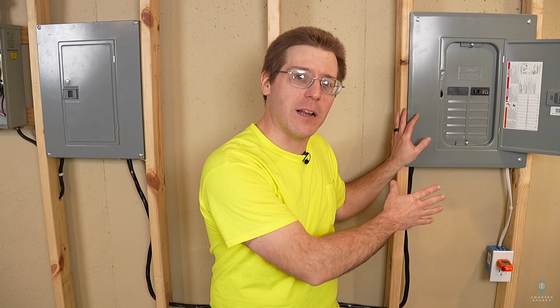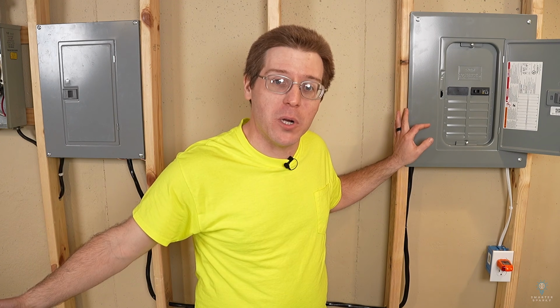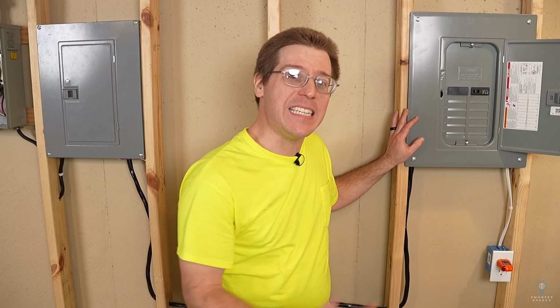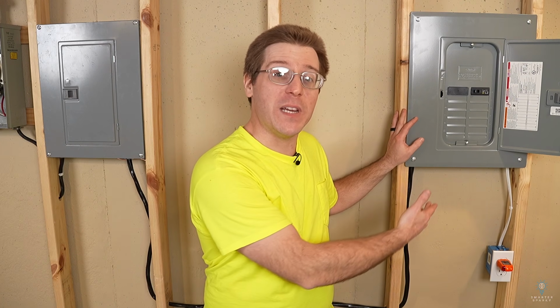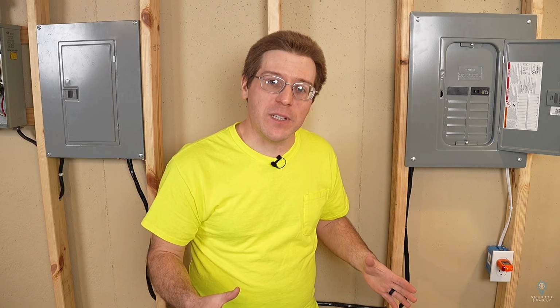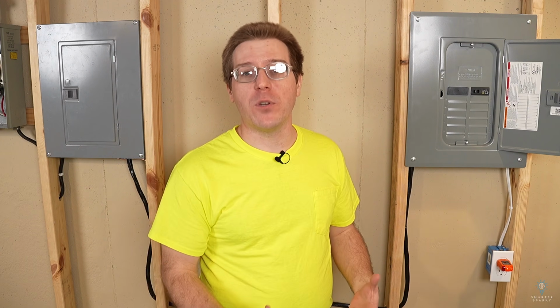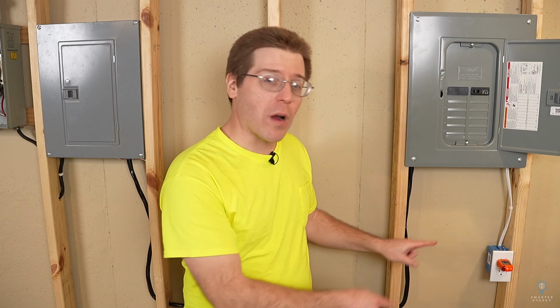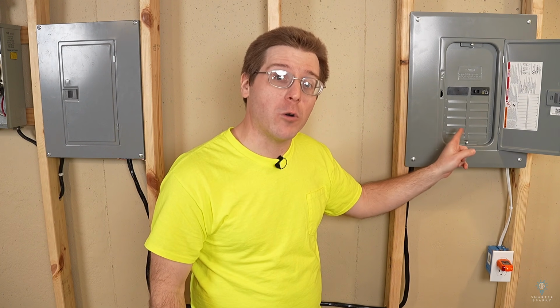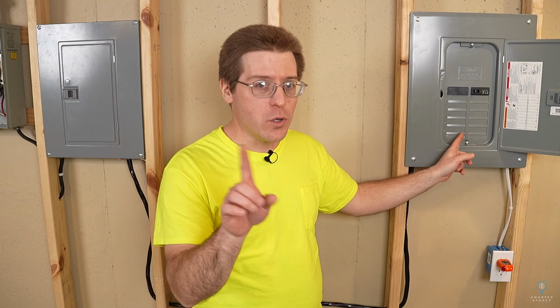There's one last question I want to answer real quick, and that would be, what if this sub panel were outside in a different building? What if this were feeding a detached garage? What if this were feeding a workshop or a garden shed or something like that? The only major difference is at that building you would have to install ground rods, and those ground rods would have to run to the ground bar in the sub panel, not the neutral bar.